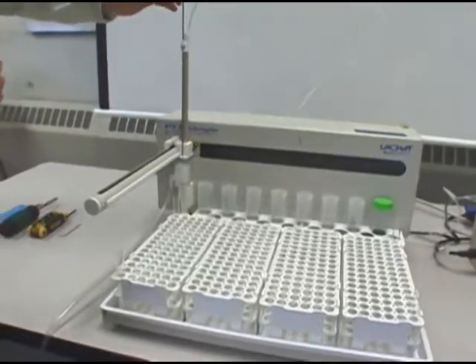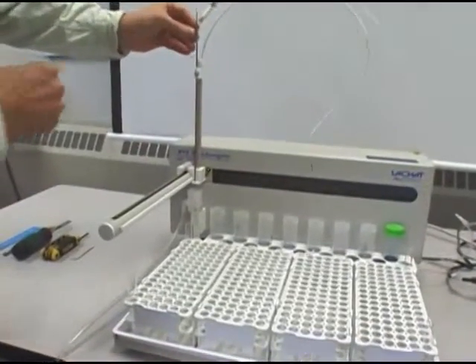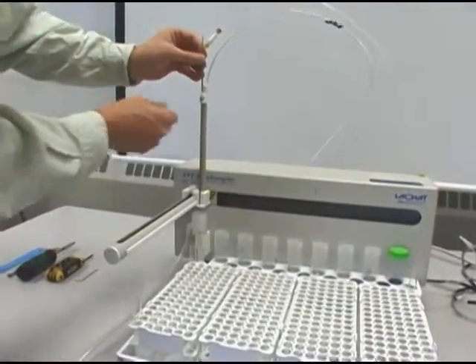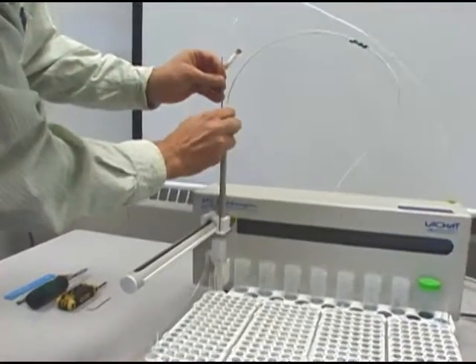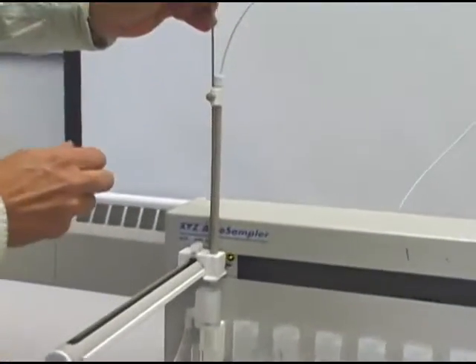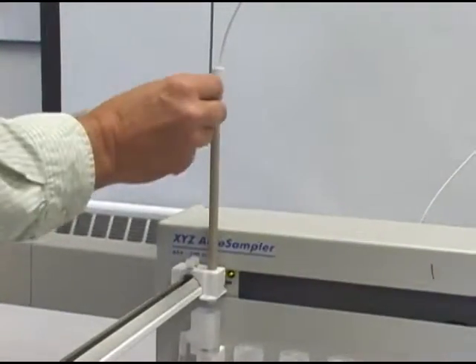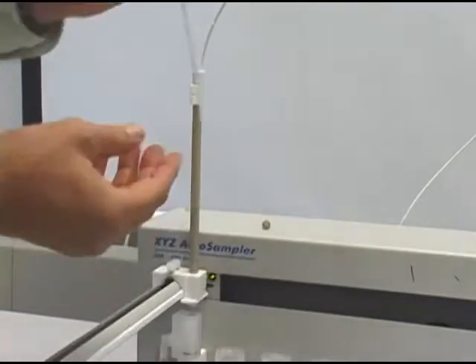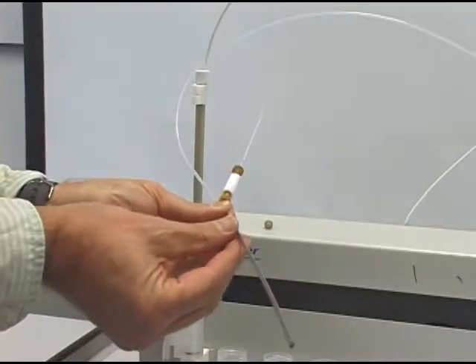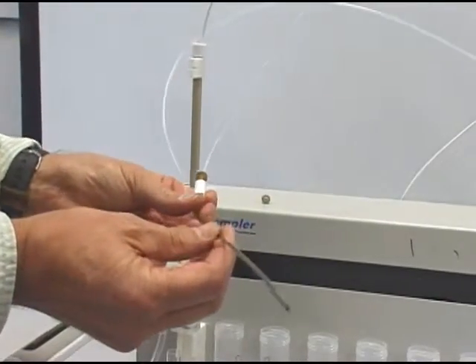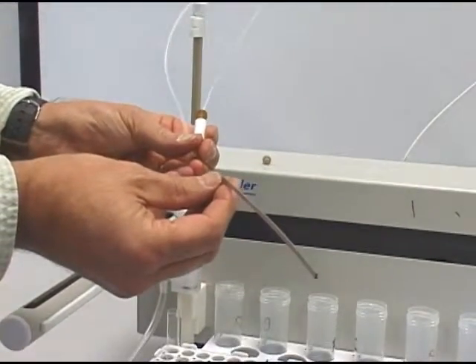First off, we're going to show you how to straighten the probe. Sometimes this may be the only thing that needs realignment. So you'll loosen this set screw and slide the probe out, and then be careful not to lose the set screw. We'll set it right there. And take a sight down the probe. You can see that this probe has been bent a bit.